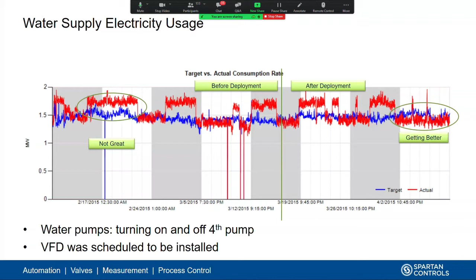So over a number of these cycles, once it was identified by the EMIS, they implemented a project to replace that 4th pump with a VFD. So now instead of running that pump at fixed speed at top speed, let's use a VFD to run it exactly where it needs to run to satisfy the pressure demand and therefore save electricity. So again, that's another means where we're using an EMIS to implement a capital project to make our system more energy efficient. Okay? So in all those cases, we're showing how an EMIS can be used to identify the high energy consumption event, but there's still potentially a lot of work involved by humans to figure out why exactly this is happening, right?